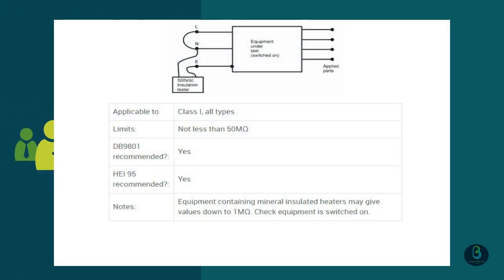These tests use AC sources to test equipment that has been preconditioned to specified levels of humidity. The tests described in the standard are type tests and are not suitable for use as routine tests.